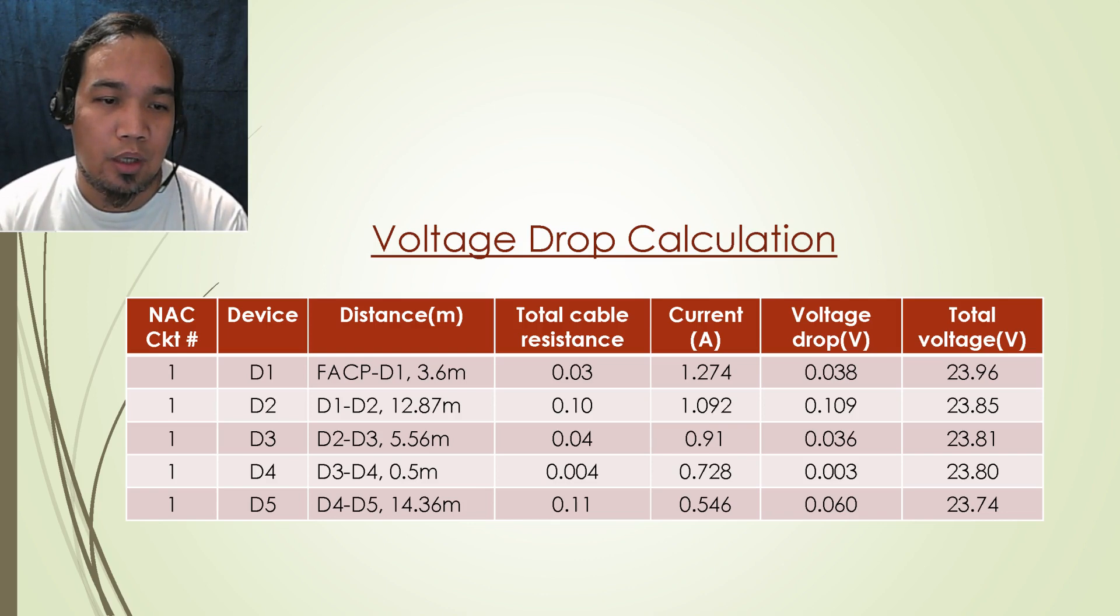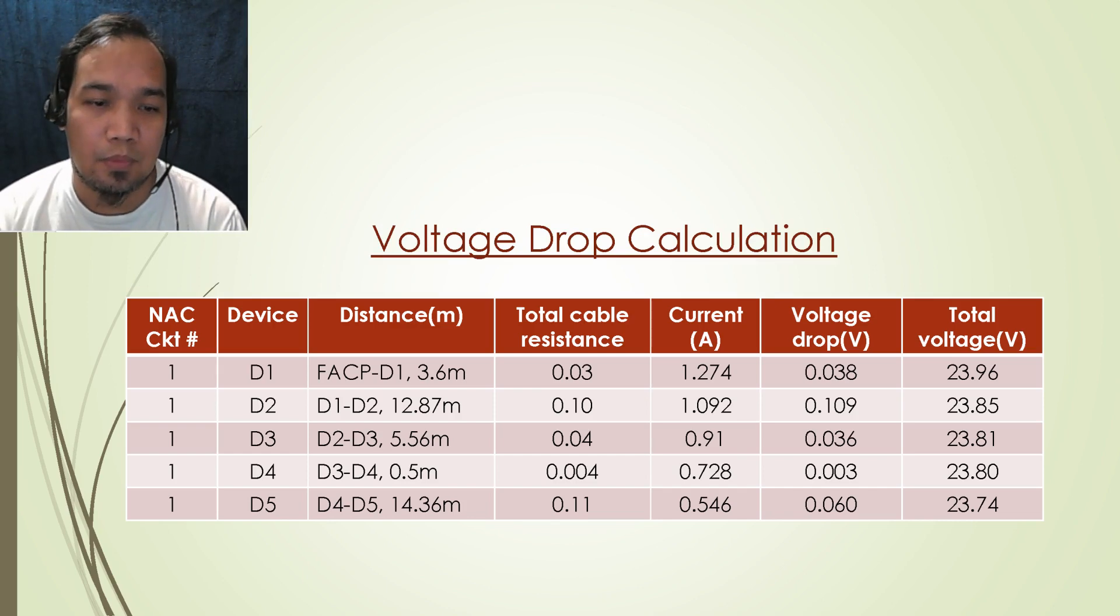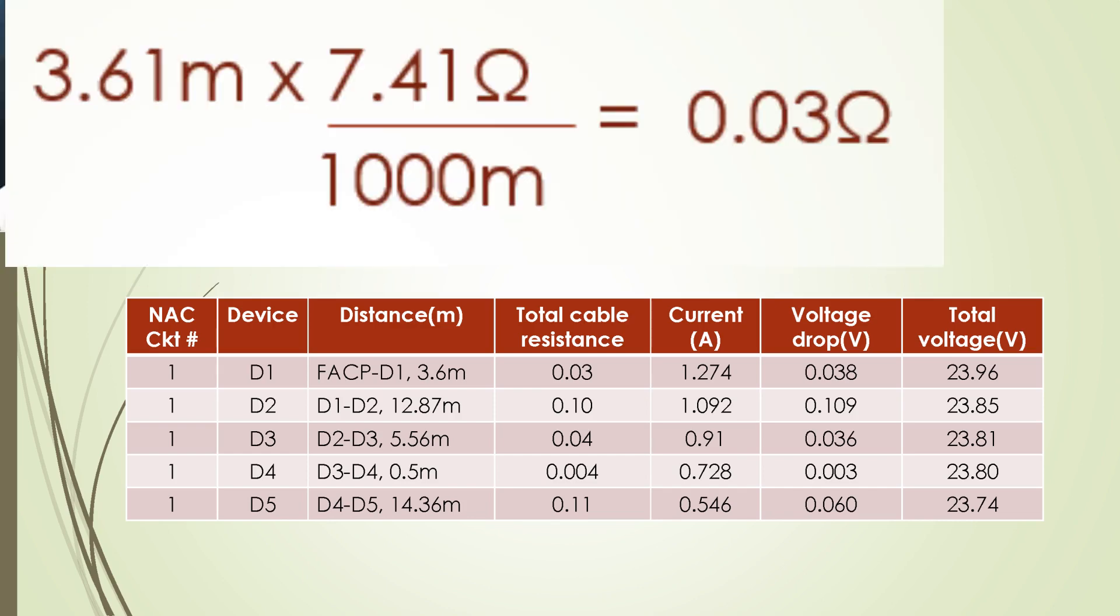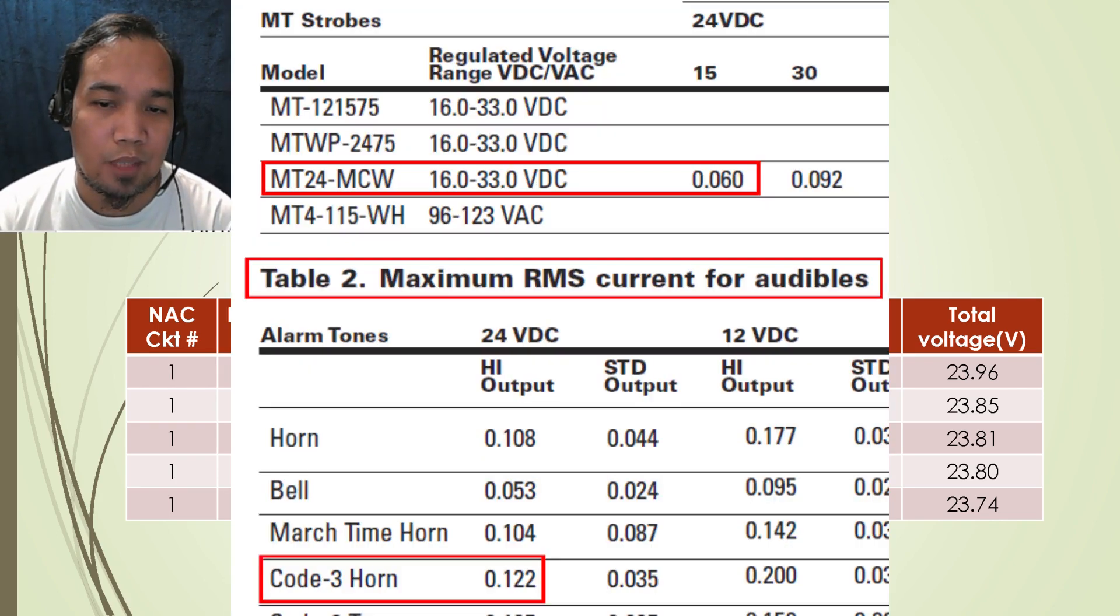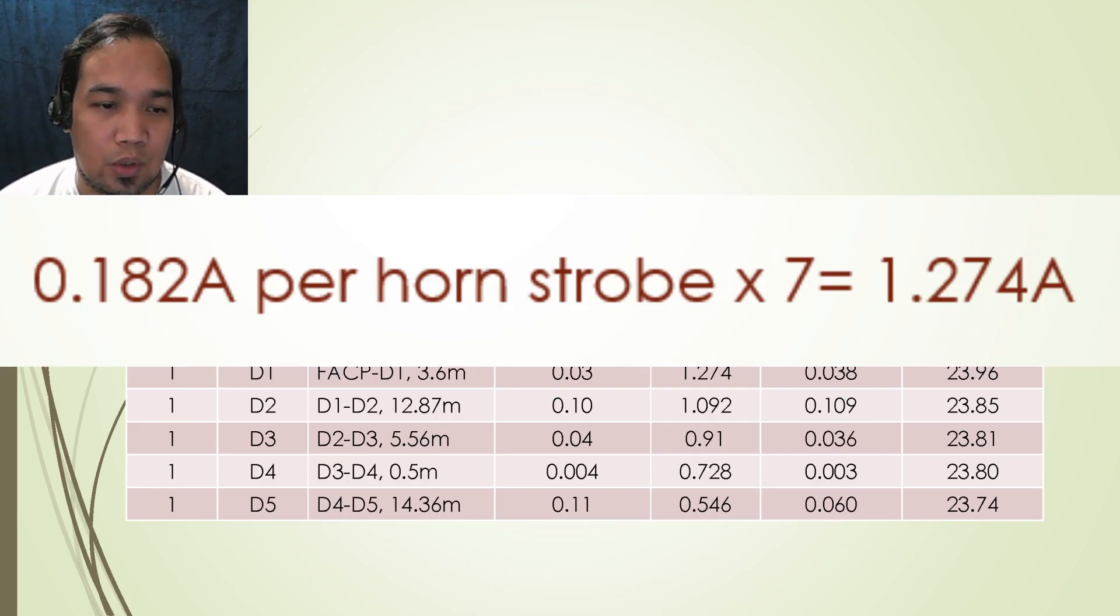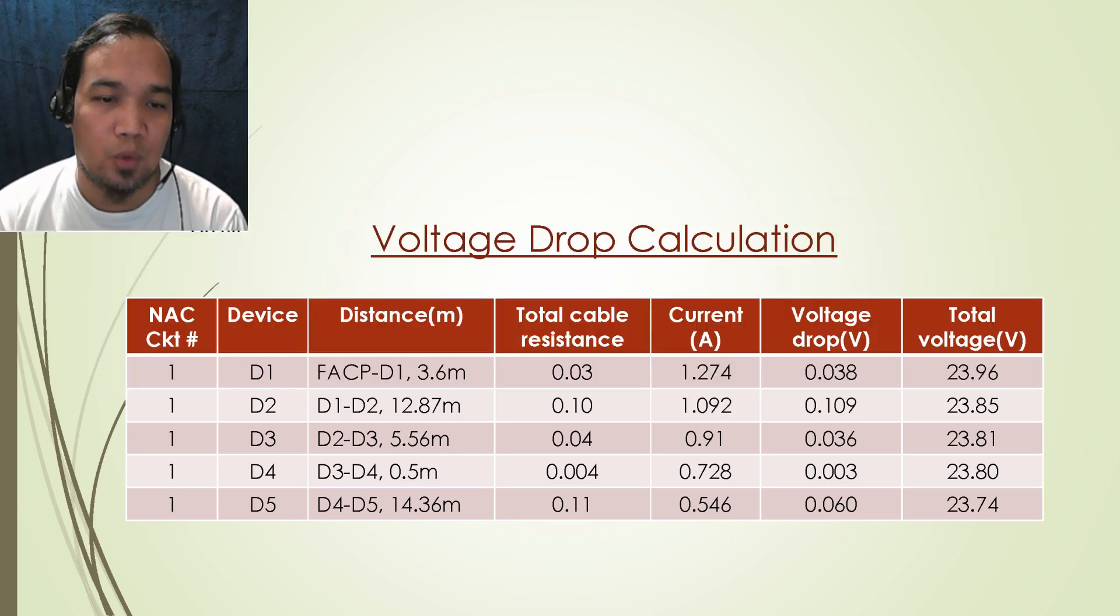The cable distance from the fire alarm control panel as the point of origin to the first device is measured with a value of 3.6 meters. Referring to the data sheet of the cable, the resistance per 1000 meter is 7.41 ohms. As an example, with this information, a value of 0.03 ohms is calculated. Now for the current, the total current of fire alarm horn strobe which is 1.274 ampere shall be used, which results to a voltage drop of 0.038 volts using Ohm's law.